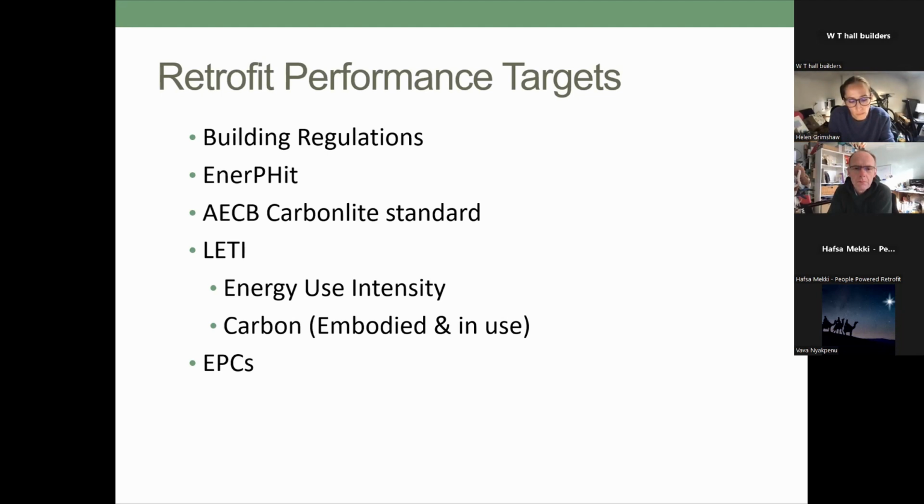On level 2, which is the equivalent of the old standard, it's been relaxed a little bit because, again, it's still really difficult to achieve. It depends on the building that you're actually working with. Historically, you had to hit 40 kilowatt hours per meter squared, and that's been revised to 50 to make it more practical to achieve at a realistic cost.